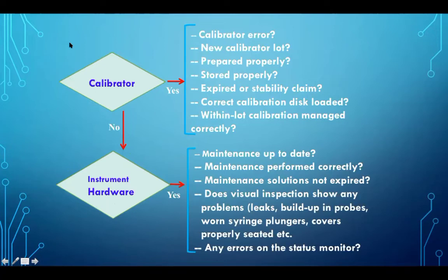Same is true for your calibrator. It is reconstituted properly, stored properly. It has not expired. And when you are storing this control, you can store it after preparing aliquots.